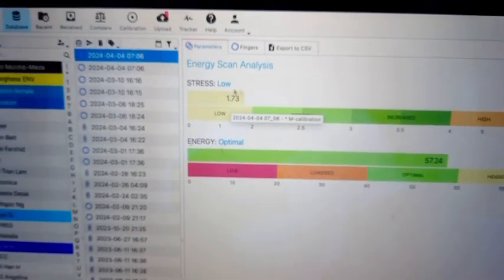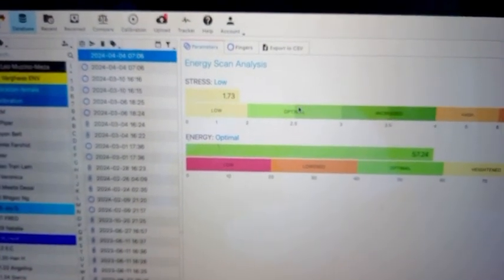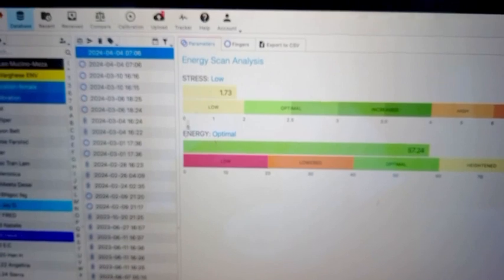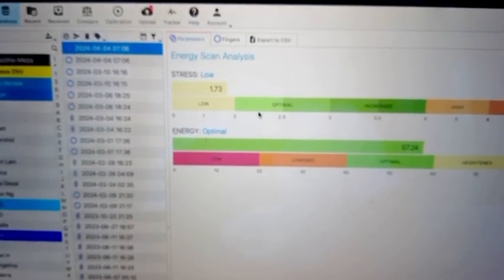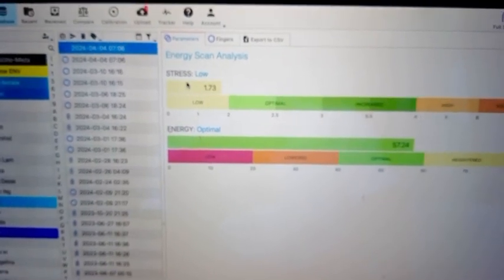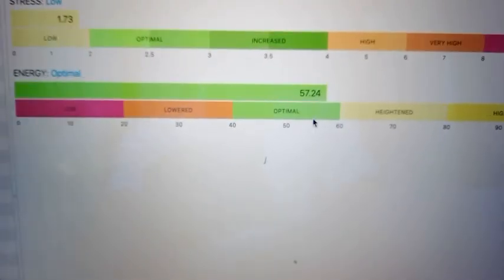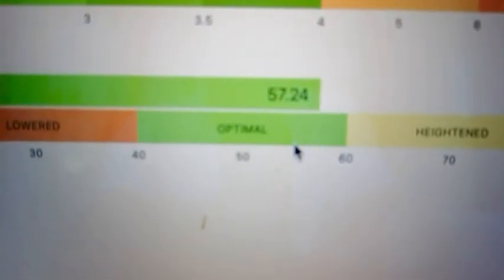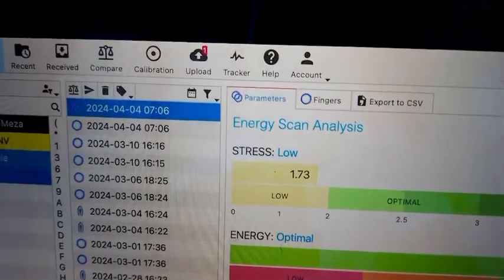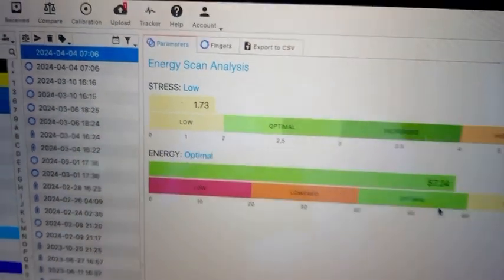hit Analyze, and the values that we see - you want this to be in the low range to the mid-optimum range here for the stress level. And then for energy, you want it to be in the optimal range, so usually over 50. That's going to be good measurements for your calibration. So once you have these values, then you know that your calibration is great and you can start using your device. If these values here are way too far off, then please contact me so I can help you guys troubleshoot it so that you can have a more successful calibration.